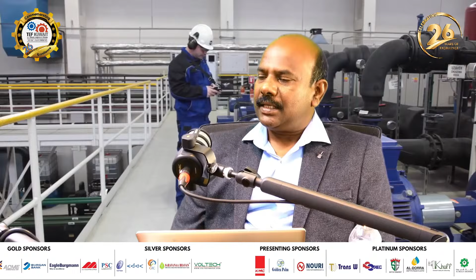For example, I will give you the gas turbine. This gas turbine operates at very high elevated temperatures, and it has certain parts exposed to high temperatures. These parts we cannot run till they fail, nor can we predict when they are going to fail. So for these items, the manufacturer recommends certain firing hours after which we have to replace those parts.